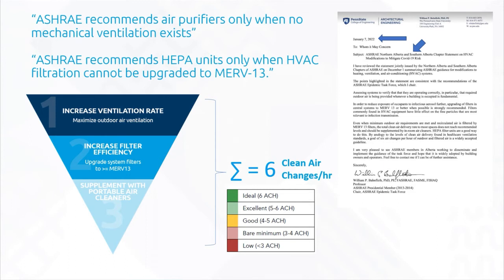I actually really feel for you guys trying to communicate these things out, because the guidance has not been clear. ASHRAE themselves have admitted this, the way they word things. So just be very careful, and we're happy to review your communications or statements like this, because we don't want you to get in trouble or get called out for statements like this that are not consistent with the guidance. So again, the guidance is, and ASHRAE is the same, it's 6 air changes per hour.